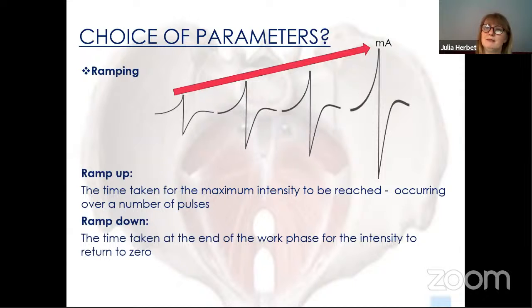The other thing that we can look at is the ramping. That's how long it takes, over that work phase, for the intensity to reach the maximum that you've set. So each pulse that's being delivered over each second is growing in intensity as it comes through, and the rate at which that gets to its maximum is the ramping. Now, if you go from 0 to 60 milliamps in a split second, that's going to be quite a shock to your muscles. Clinically, I would use half a second, 0.5 of a second, but there are programs that are preset at 1 second or 2 seconds.